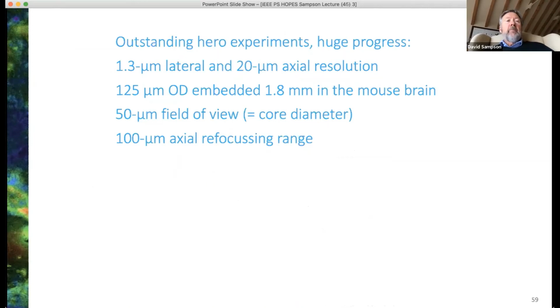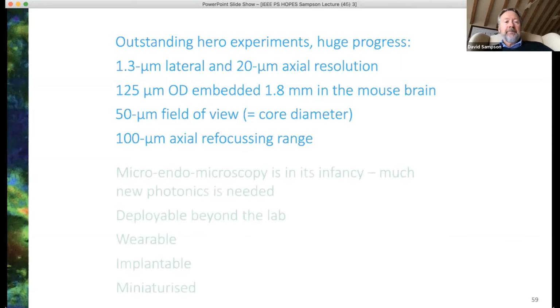It achieved 1.3 micron lateral and 20 micron axial resolution. It was only 125 microns in outer diameter. It was embedded millimeters into the mouse brain. It has a field of view which is equal to the core diameter of the multimode fiber. But it was even able to refocus computationally across a 100 micron axial range. So an outstanding piece of work. But as you can see, not quite yet able to be taken to the field.